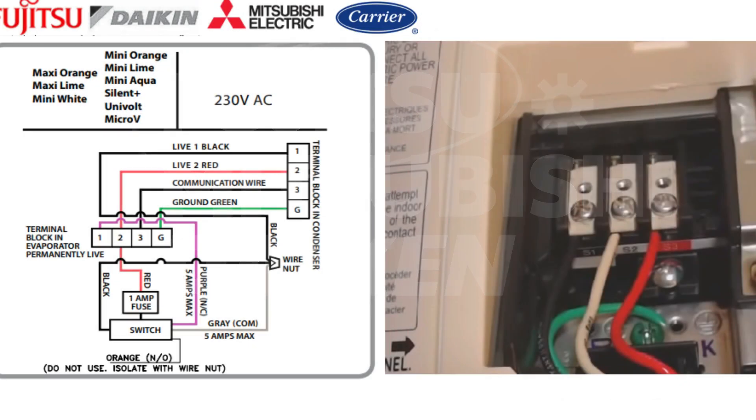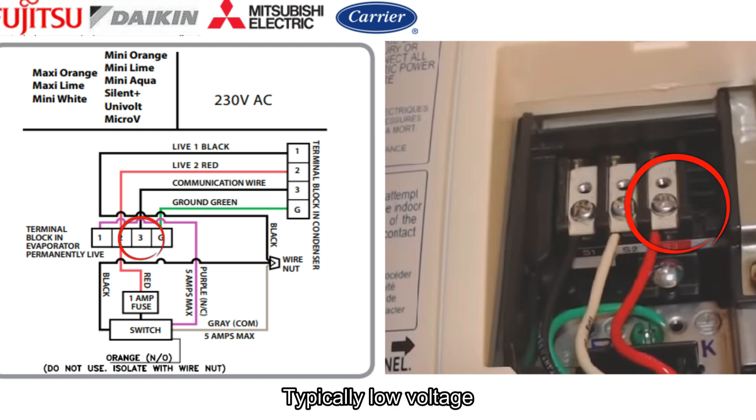What we're looking at here is the wiring schematic directly from Rector Seal on how to wire these units in Fujitsu, Daikin, and Mitsubishi. Some LG systems will be like this as well. What makes all these systems kind of the same is that terminal blocks one and two on the indoor head are your power supply wires — there's 120 volts on each one of these legs. Number three is the communication wire.